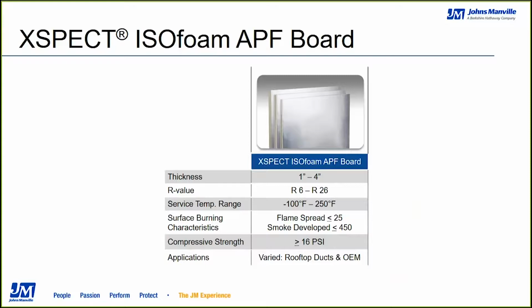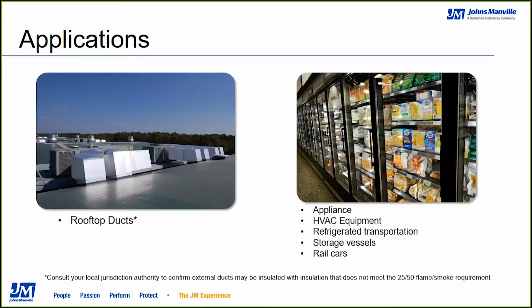Compressive strength is quite good at 16 pounds per square inch, and it is used in a number of applications we'll talk about here. So for mechanical insulations, it's typically used on an exterior rooftop duct. The reason for exterior ducts primarily is that often the products for mechanical insulations require a 25/50 rating. In this case, the product does not, so it's most often used externally. For OEM applications, though, the product can be used in a variety of different applications, like appliance, HVAC equipment, transportation for refrigerated cars, storage vessels, or maybe rail cars.